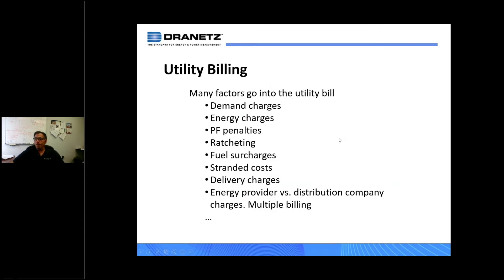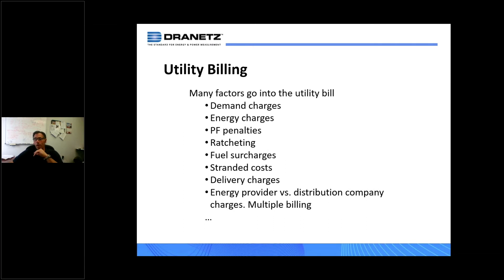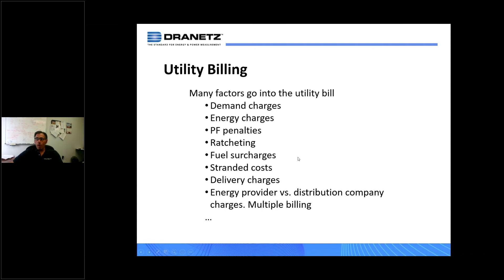Wrapping up the energy part: what goes into billing? Different utilities do things a little differently, but typically there's a demand charge, an energy charge, power factor penalties, and ratcheting — meaning once you hit a particular tier, you pay a higher rate that won't go down until the billing period resets. You could also have fuel surcharges, stranded costs, and delivery charges. In some cases you may have multiple providers — someone you buy energy from and a separate distribution company — resulting in multiple bills. All these go into understanding your energy costs.